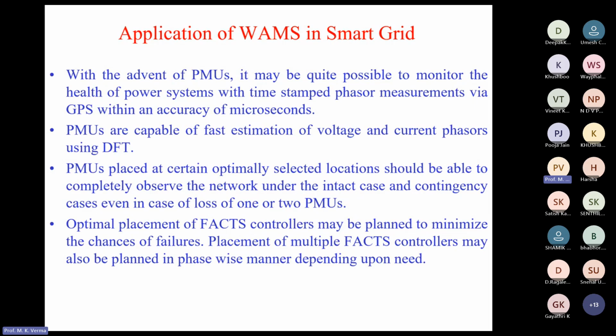Now, with the advent of phasor measurement units, I have already told that it is possible to monitor the health of the system through time-stamped measurements via GPS. These measurements are synchronized, and we perform measurements with the accuracy of microseconds. And these PMUs are able to have the fast estimation of voltage and current phasors using discrete Fourier transform. At PMUs, you cannot place every location. With the minimum number of locations placed, you should be able to completely observe the system. Completely observe the system means we can completely monitor the whole system. Even with the loss of 1 or 2 PMUs, you should be able to monitor the system.